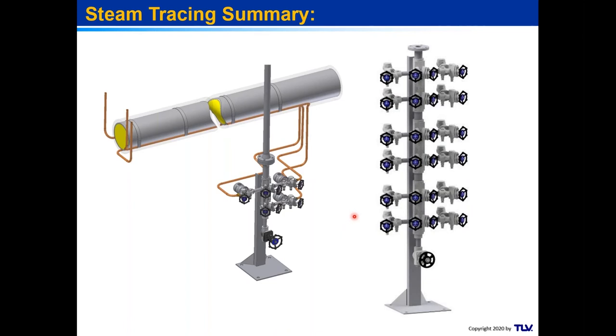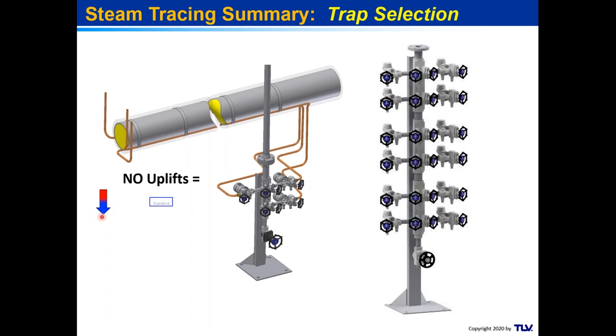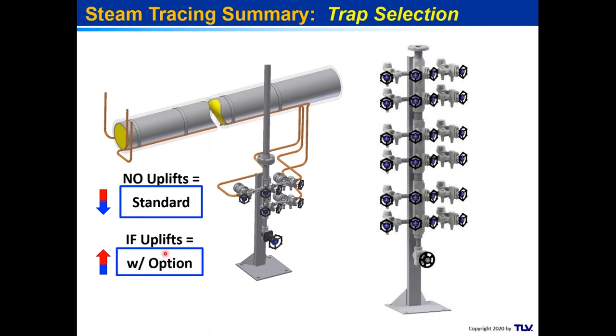To summarize trap selection: gravity feed with blue at the tip of the flow arrow — use a standard steam trap. Long horizontal runs with mixed steam and condensate at the tip — potential steam locking, use technology with a controlled steam lock release. Any uplift anywhere in the thermal circuit or lifting up to the steam trap — steam lock condition, select a trap with a steam lock release option.